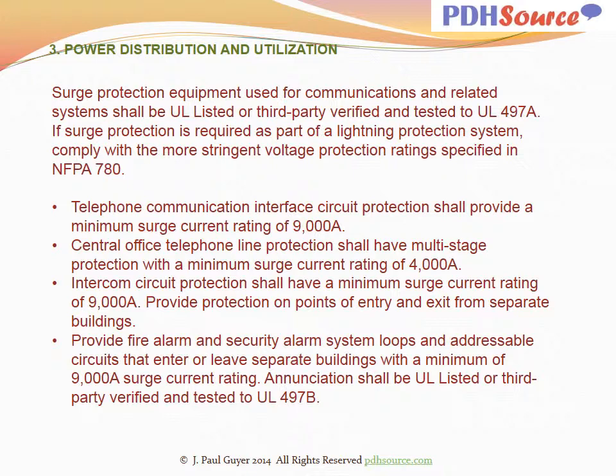Intercom circuit protection shall have a minimum surge current rating of 9,000 amps. Provide protection on points of entry and exit from separate buildings. Provide fire alarm and security alarm system loops and addressable circuits that enter or leave separate buildings with a minimum of 9,000 amps surge current rating. Annunciation shall be UL listed or third party verified and tested to UL497B.